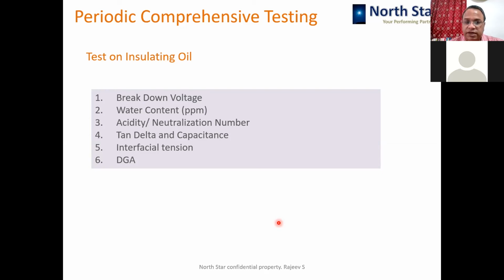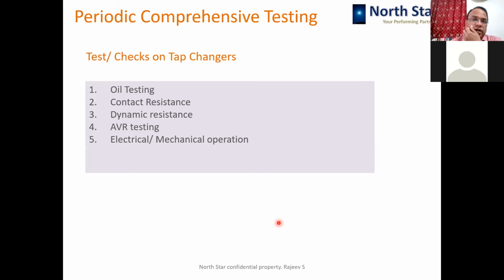Okay, so tan delta and capacitance of the oils should be done separately. Interfacial testing should be done. So these tests are to be performed on the oil from time to time. Okay, when it comes to OLTC oil testing, OLTC oil has to be tested more frequently compared to the transformer.